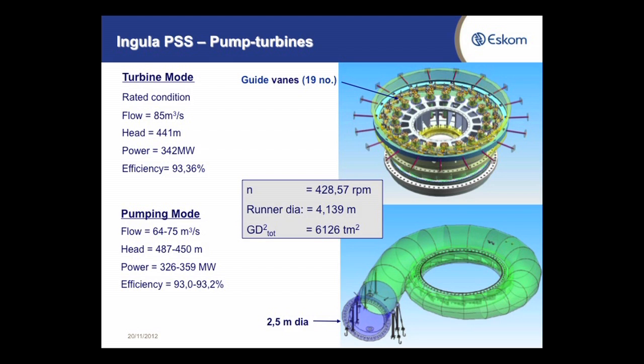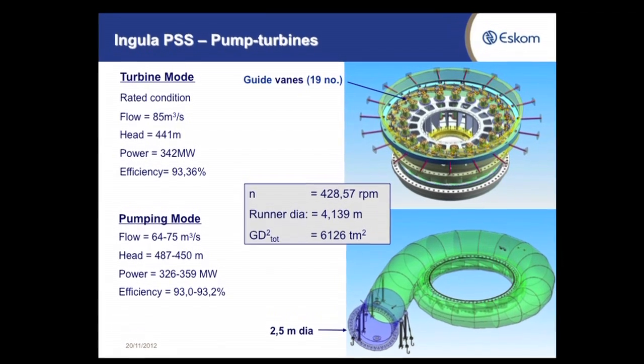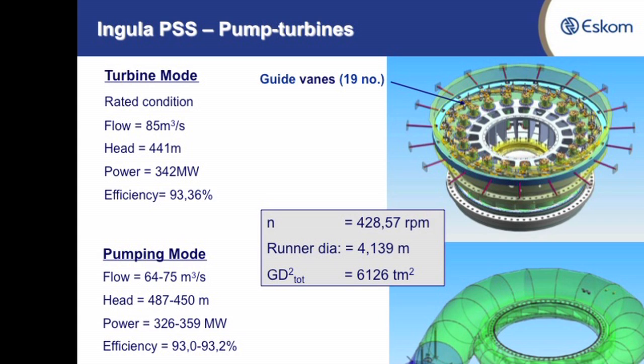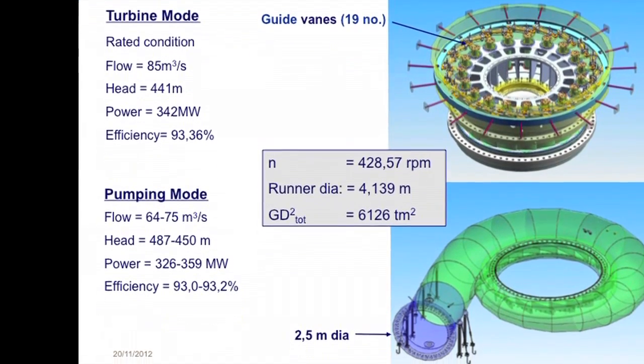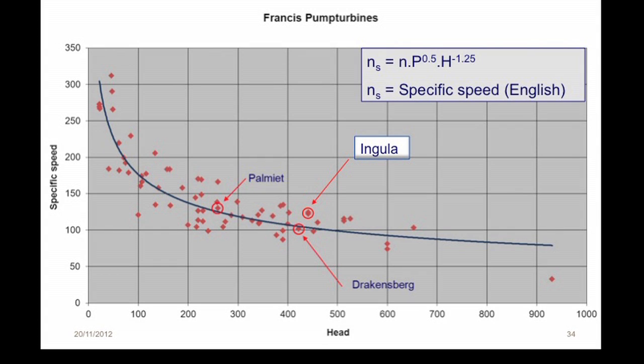And then we got the final version, where the efficiency at 85 cubic meters per second per machine at that head is 93%, which is quite a high efficiency. And at pumping it follows a similar figure. Now when you have a contract with your supplier, you set certain aims, and he then tenders to supply these high efficiencies, and there's a penalty if he can't reach the efficiency after the scheme has been built. We will then get a reduction. Plotting the Ingula specific speed graph, there is nothing out of the ordinary, a bit higher than the Drakensberg and the Palmiet scheme.